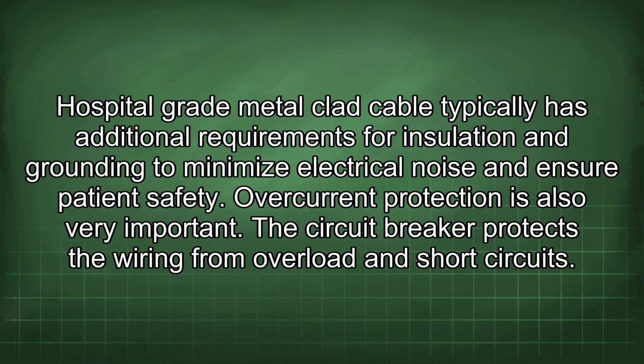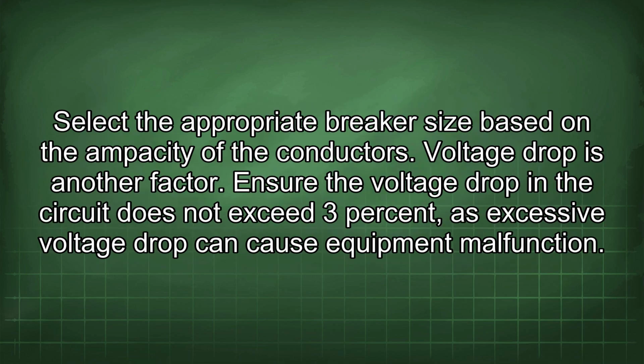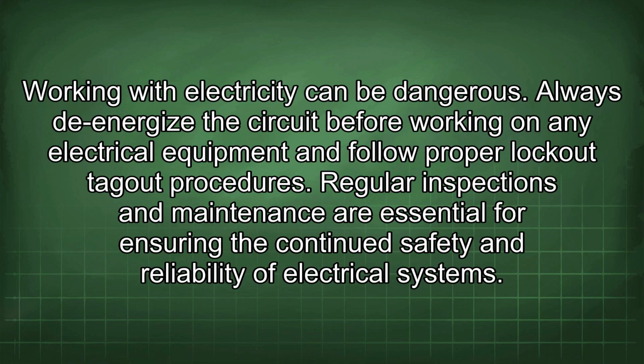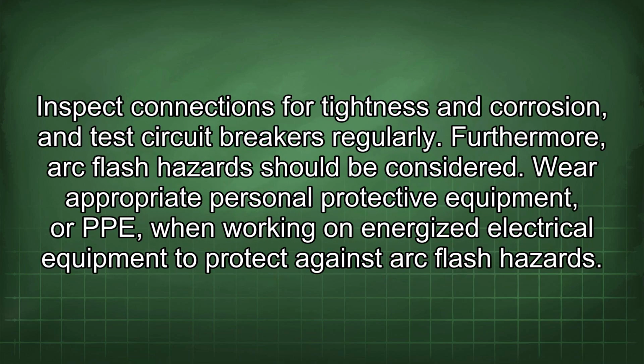Overcurrent protection is also very important. The circuit breaker protects the wiring from overload and short circuits. Select the appropriate breaker size based on the ampacity of the conductors. Voltage drop is another factor. Ensure the voltage drop in the circuit does not exceed 3%, as excessive voltage drop can cause equipment malfunction. Working with electricity can be dangerous. Always de-energize the circuit before working on any electrical equipment and follow proper lockout-tagout procedures. Regular inspections and maintenance are essential for ensuring the continued safety and reliability of electrical systems. Inspect connections for tightness and corrosion and test circuit breakers regularly.